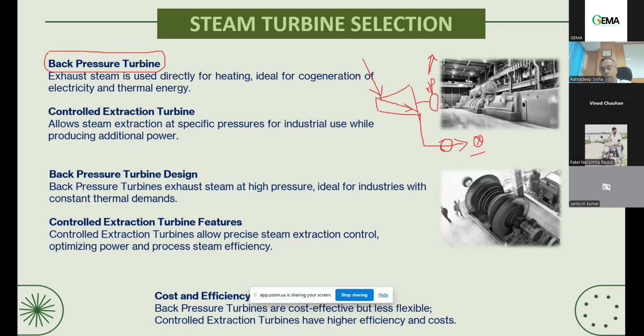Fluctuation and accuracy, how accurate we are in our estimation of power and steam, is very important. If we start over-designing, suppose I decide my power demand is 14 megawatt and I purchase a turbine of 17 megawatt, and my steam demand remains at say 45 TPH, and I am still at 45 TPH. So if my power demand is less, I cannot take 45 TPH. We all need to understand that. I think I am making it clear.